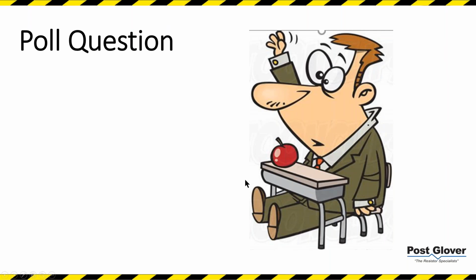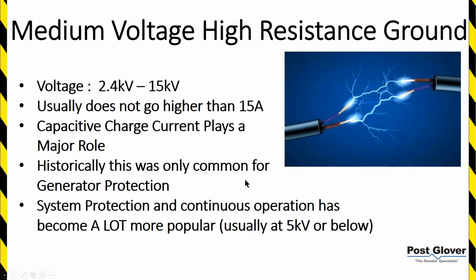All right, let's go ahead and move on then. So medium voltage high resistance ground. Typically we're talking about voltages anywhere above 600 volts, at least from my perspective, from above 600 volts to 15 kV, but most likely you're going to see 2.4 to 15 kV. It usually does not go higher than 15 amps. We've seen requests for higher than that, but not usually at medium voltage. And honestly, at some point you have to ask yourself, is this really high resistance grounding anymore?